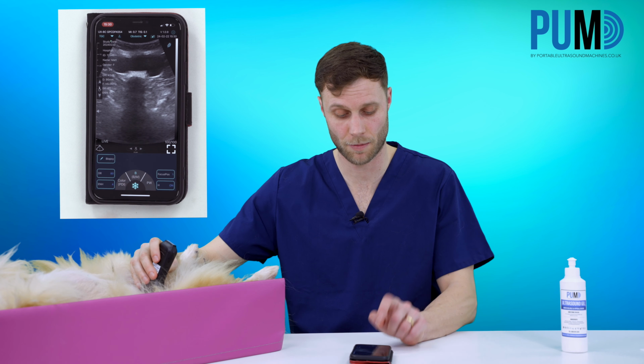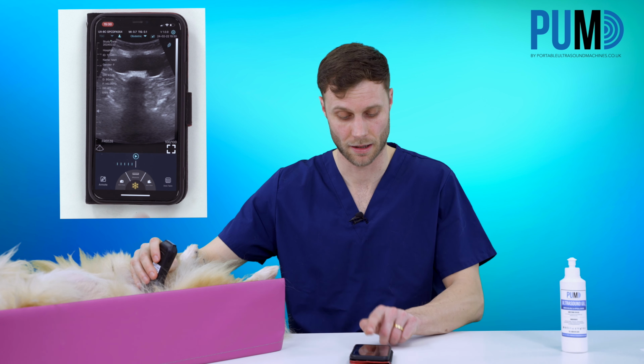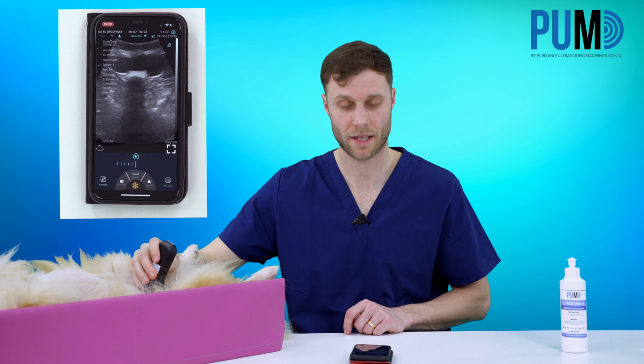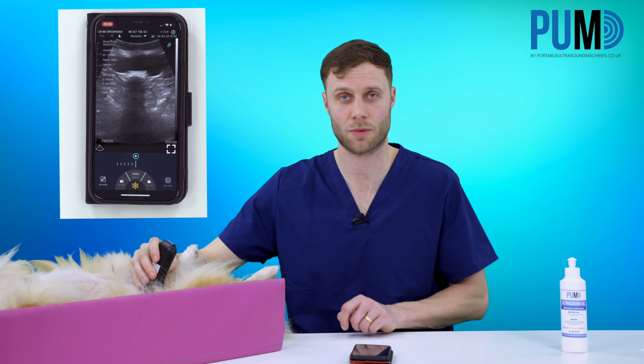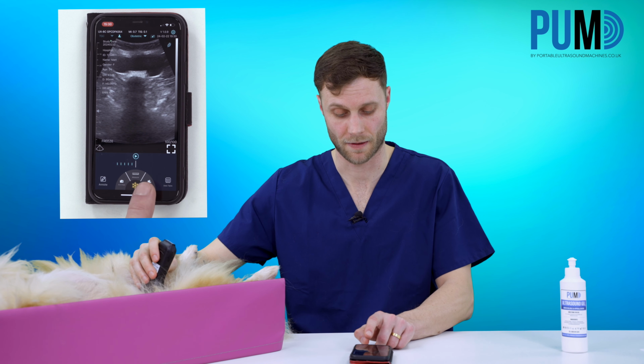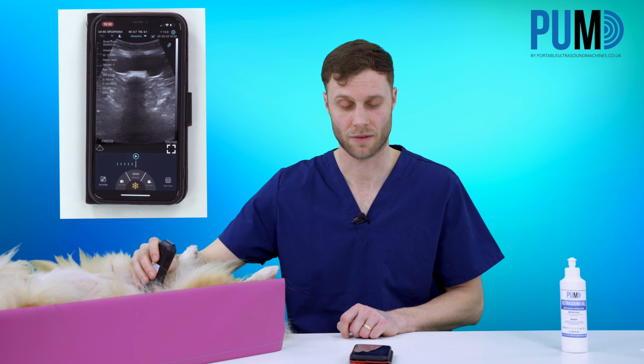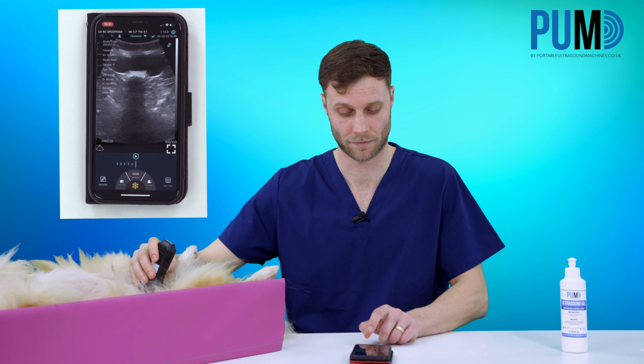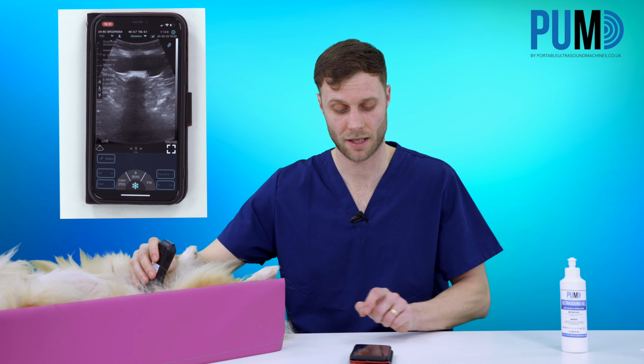When you're scanning and you're happy with the image you've got, you can then save that image. To do that, hit the freeze button on the bottom. That's the little icicle you can see there. Then you'll have two options: save image, which will be a still image, or save video, which will save a cine clip. If I hit the save video here, you'll see it will just load, and that will save into your phone or tablet storage. So you can find that later and you can share that if you need to, or you can take it off and put it onto a hard drive to make sure it's safe. To start scanning again, just hit the unfreeze button.